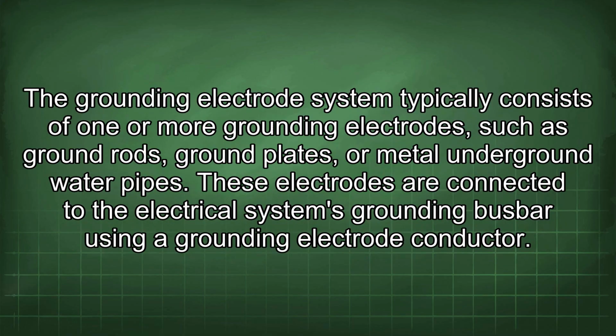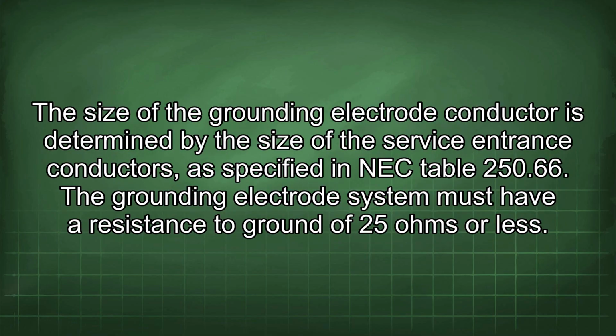The grounding electrode system typically consists of 1 or more grounding electrodes, such as ground rods, ground plates, or metal underground water pipes. These electrodes are connected to the electrical system's grounding bus by using a grounding electrode conductor. The size of the grounding electrode conductor is determined by the size of the service entrance conductors, as specified in NEC Table 250.66. The grounding electrode system must have a resistance to ground of 25 ohms or less.